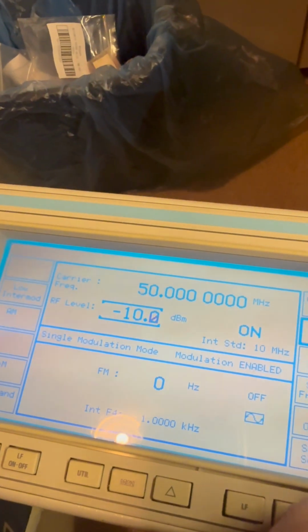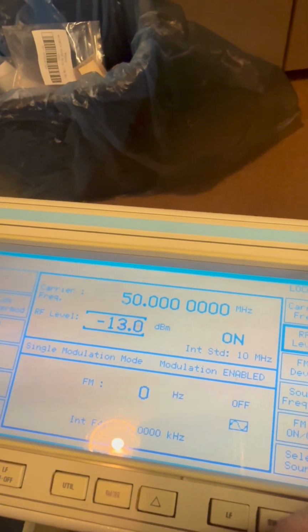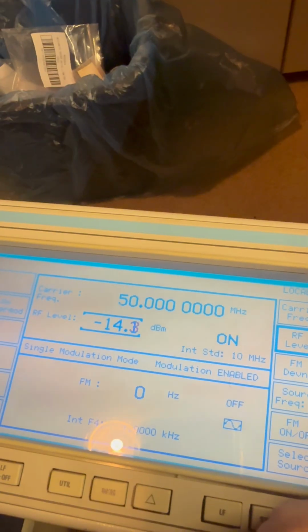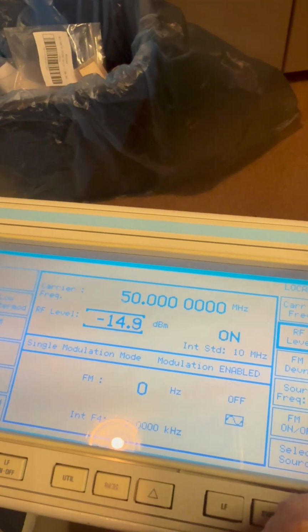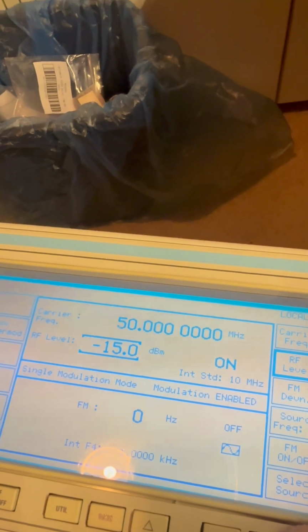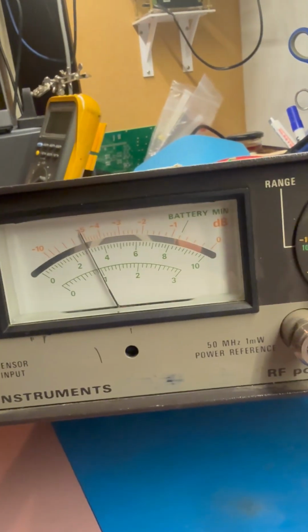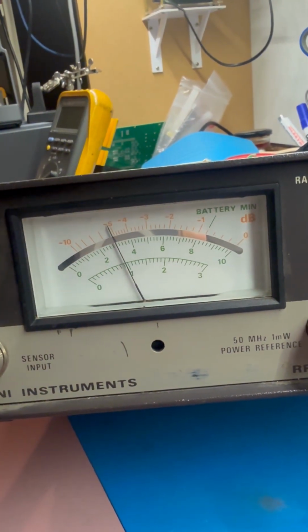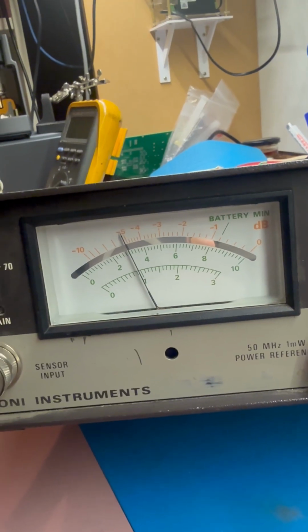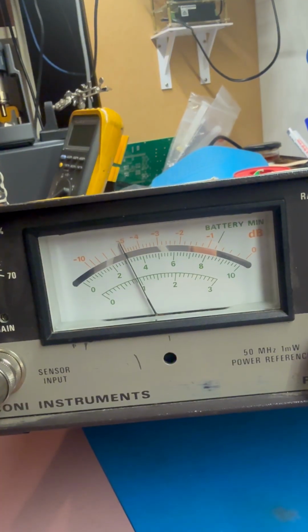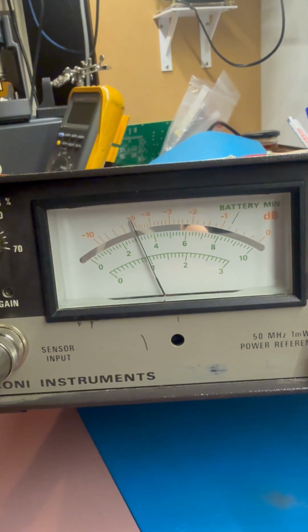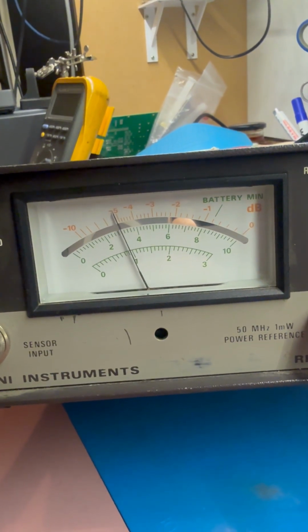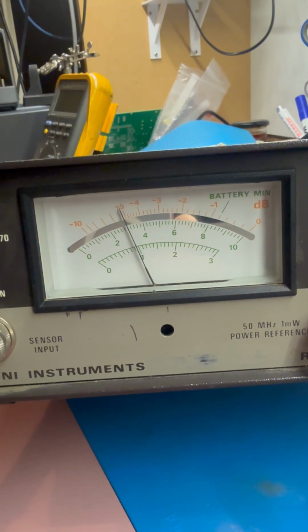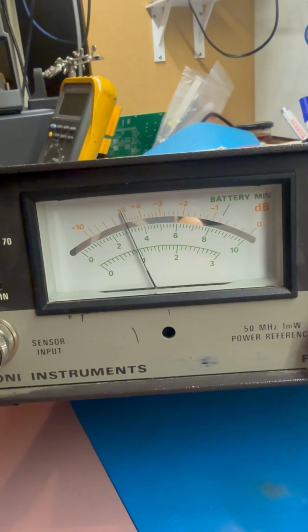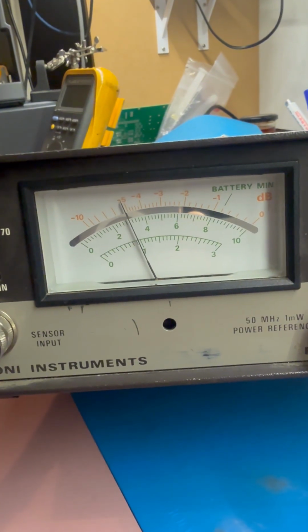And we adjust that to minus 15 dBm. There we go, minus 15 dBm. And we go back, and that's showing us our minus 5 dBm again, reading by the sensor. So minus 10, minus 5 gives us minus 15 dBm. So that's how I'm testing my sensors, and I think this particular sensor is working okay. It's doing all the things that it should be.